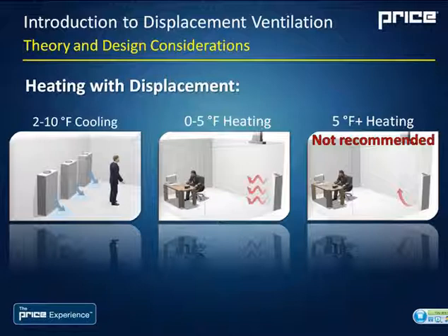Now the final scenario here is when you exceed that 5 degrees, and typically we don't recommend this scenario simply because that air now lacks the velocity to overcome buoyancy. So the warm supply air is going to be less dense than the room air, and it's just going to want to go straight up because it has very little velocity coming off of that diffuser to mix into the room.